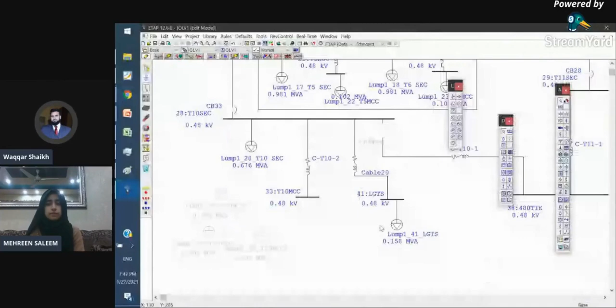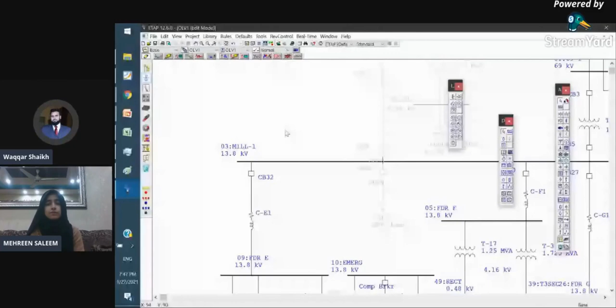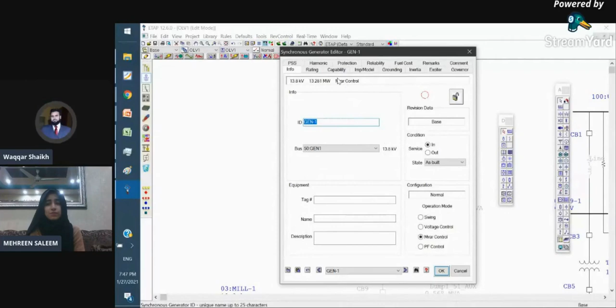For any generator, there is a curve given by the manufacturer, called the generator capability curve. This curve has to be given into the ETAP software, in the capability area, where you have to model the curve. So first, you have to understand the concept: any generator is rated for a given capability range.